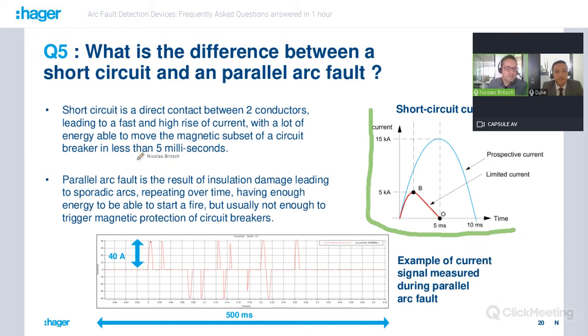And parallel arc fault is the result of insulation damage leading to sporadic arcs repeating over time, but having enough energy to be able to start a fire. But usually not enough to trigger the magnetic protection of the circuit breaker. And here below on this graphic, you have an example of a signal recorded during a parallel arc fault. And as you can see, the current values are much lower than, of course, a short circuit. We are talking, in this example, of a peak value of 40 amps. And also the time window is much longer, because here you have 500 milliseconds. So it's a fault that will repeat over time, but in the end it can lead to an electrical fire, and that's why it's very important to use arc fault detection against this kind of fault, the parallel arc fault.